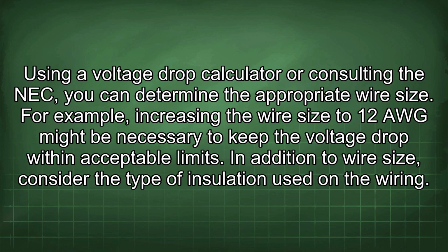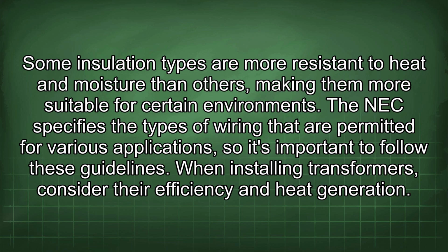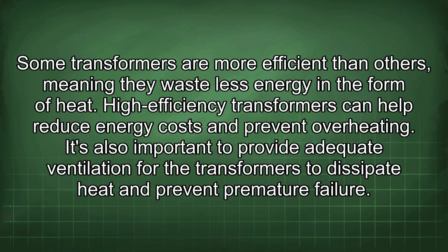In addition to wire size, consider the type of insulation used in the wiring. Some insulation types are more resistant to heat and moisture than others, making them more suitable for certain environments. The NEC specifies the types of wiring that are permitted for various applications, so it's important to follow these guidelines. When installing transformers, consider their efficiency and heat generation. Some transformers are more efficient than others, meaning they waste less energy in the form of heat. High-efficiency transformers can help reduce energy costs and prevent overheating. It's also important to provide adequate ventilation for the transformers to dissipate heat and prevent premature failure.